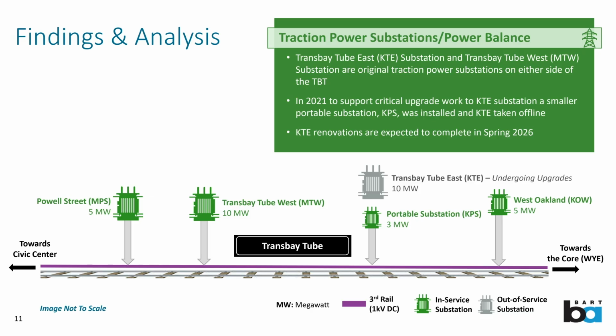To facilitate that upgrade, BART introduced a portable substation known as KPS. We looked extensively at the dynamics of this and the records, and determined this portable substation has been used elsewhere successfully on the system. Interestingly, it has a 5 megawatt rectifier supplied by a 3.2 MVA transformer, so the overall capacity is noted on the diagram as 3 megawatts.